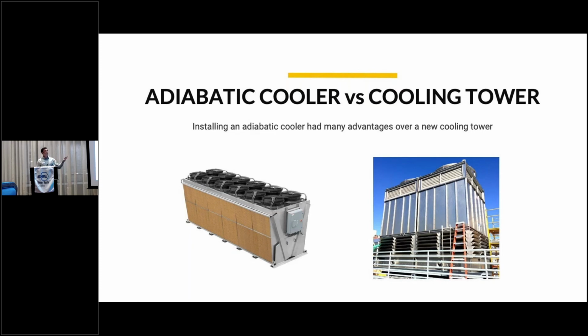The reason we chose an adiabatic cooler is because it has increased heat rejection efficiency in the system, because the mesh sides of it can have water sprayed onto it as the air comes down. So the air coming in is at a cold enough temperature that the heat transfer is far superior than just a dry cooler, and we don't have to deal with chemical treatment because there's no standing water.